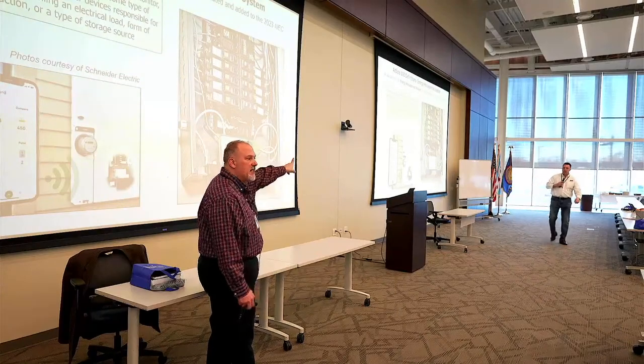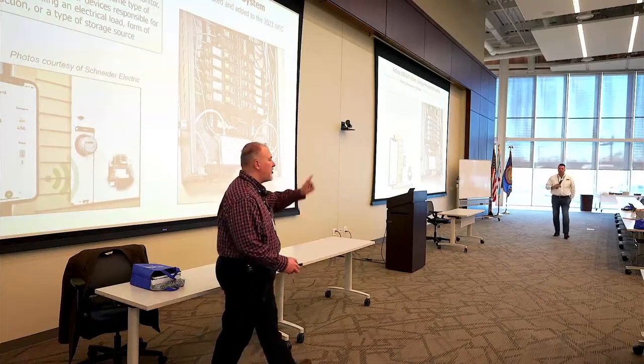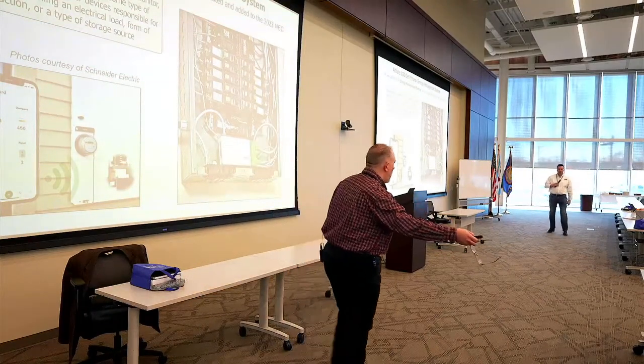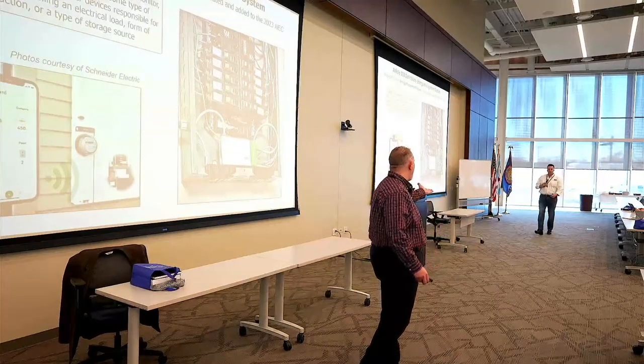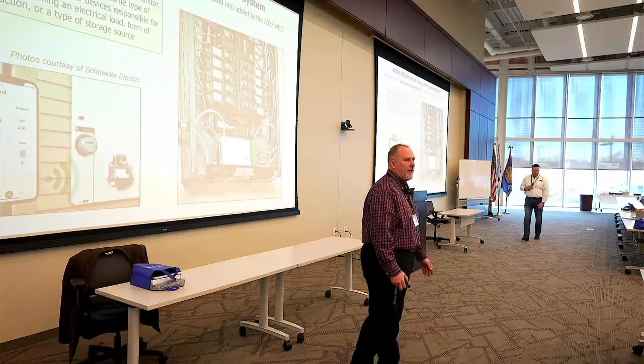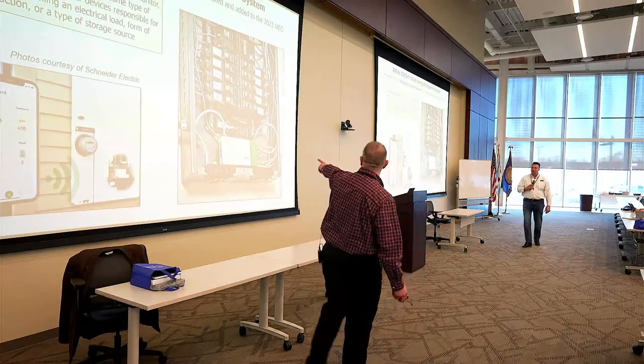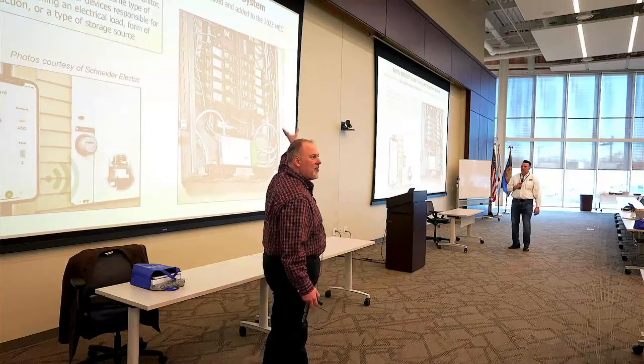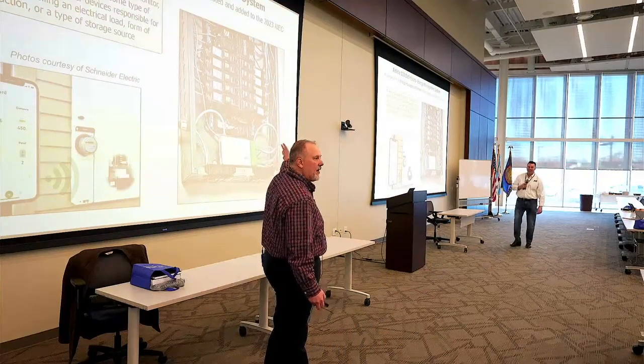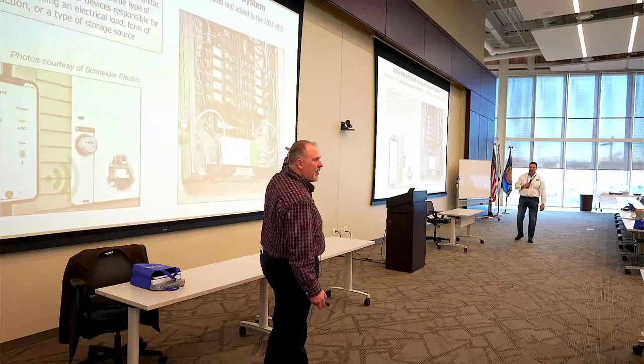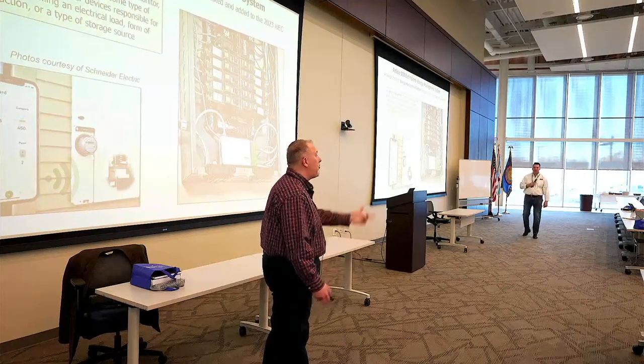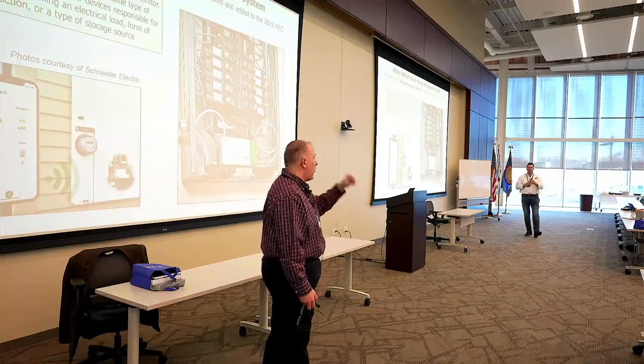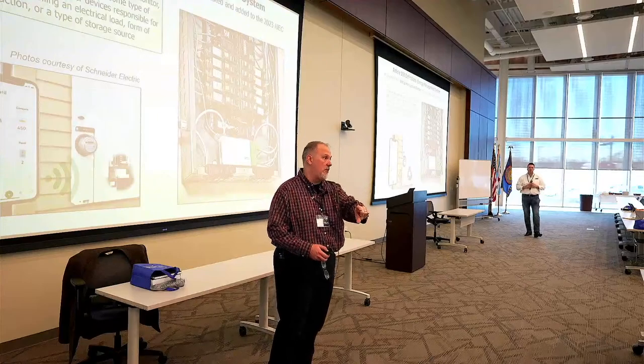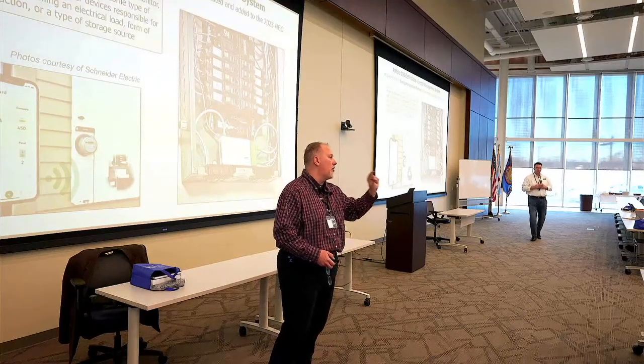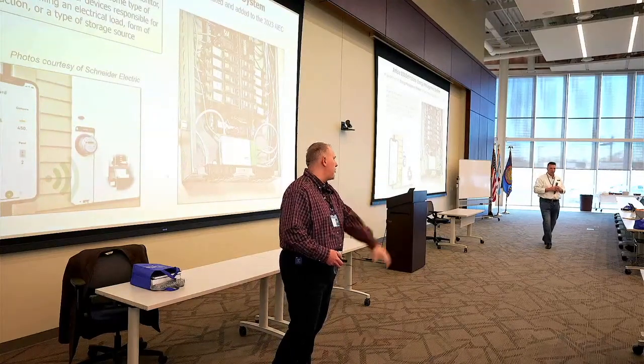So when you see this type of equipment in the field, you know you've got Chapter 3, Chapter 4: 408 for panel boards, 312 for cabinets. And remember, in this picture, the panel board is not the entire assembly - the panel board is just the guts. That's installed in an enclosure. And they created a new defined term in Article 100 for an enclosed panel board, in addition to just the word panel board, because of the way it's used in the code.